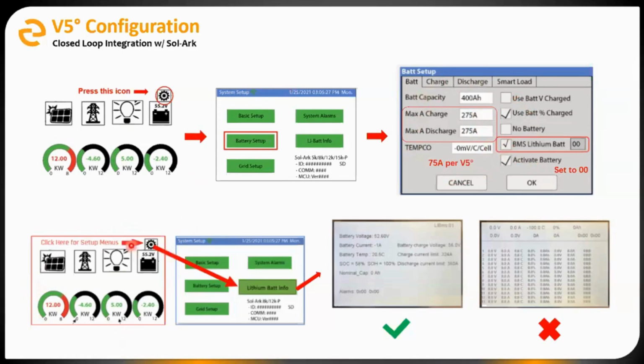You'll go back to the main menu of Sol-Ark, click the settings option again. You should now see this button, Lithium BAT Info or LI BAT Info. You'll tap that option and you'll see one of two things. If you see this first screen on the left, that means everything's good. That means that the batteries are talking to the inverter and vice versa. You can actually look, might be kind of hard to see here on the screen, but charge current limit, discharge current limit, those two numbers should usually line up with 75 amps per battery.